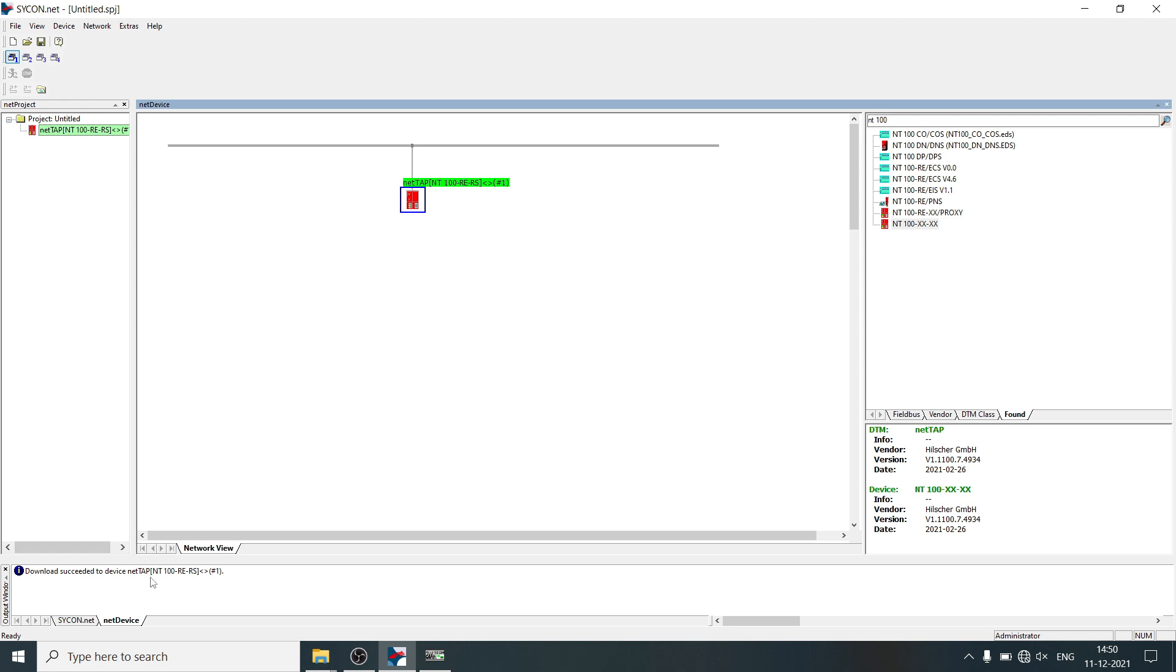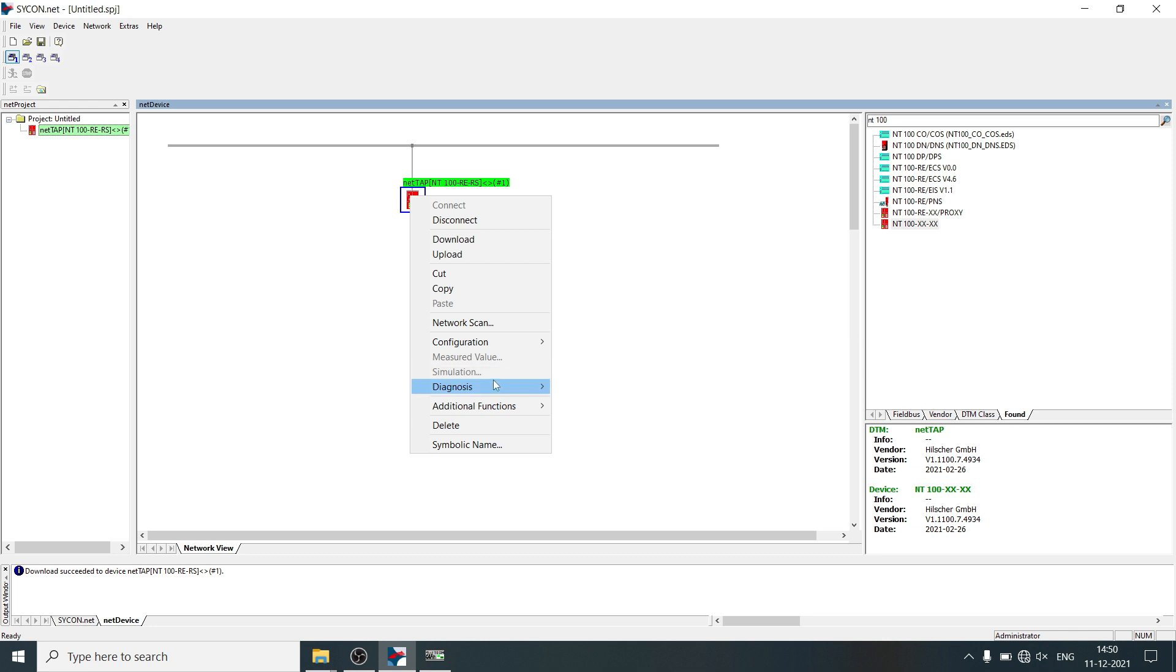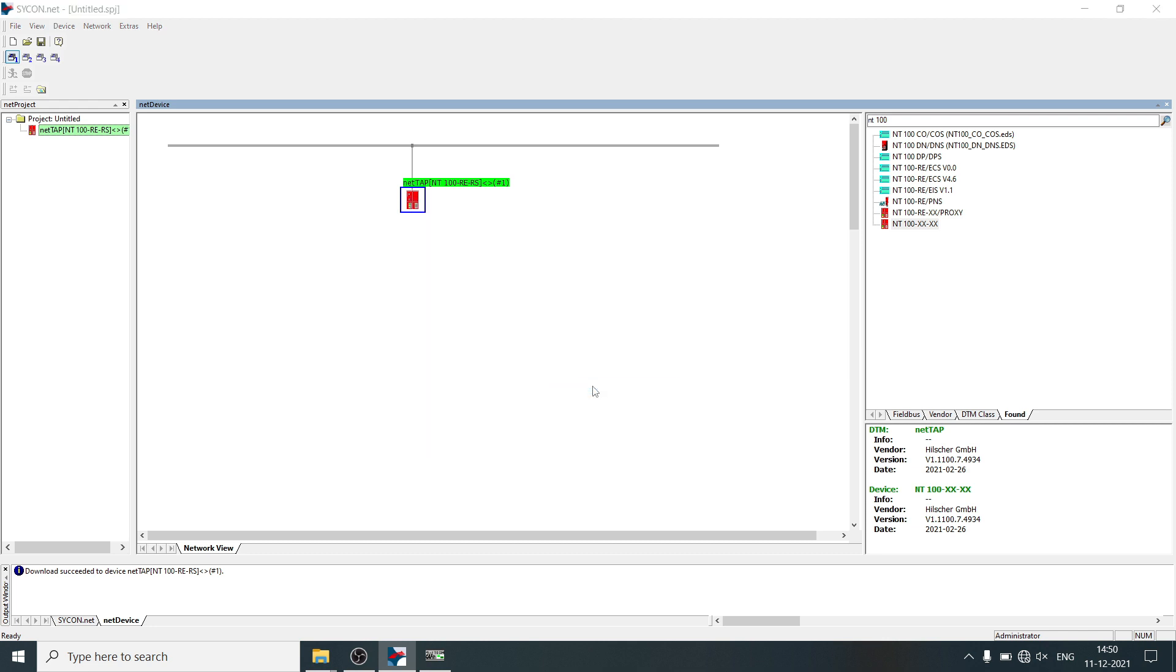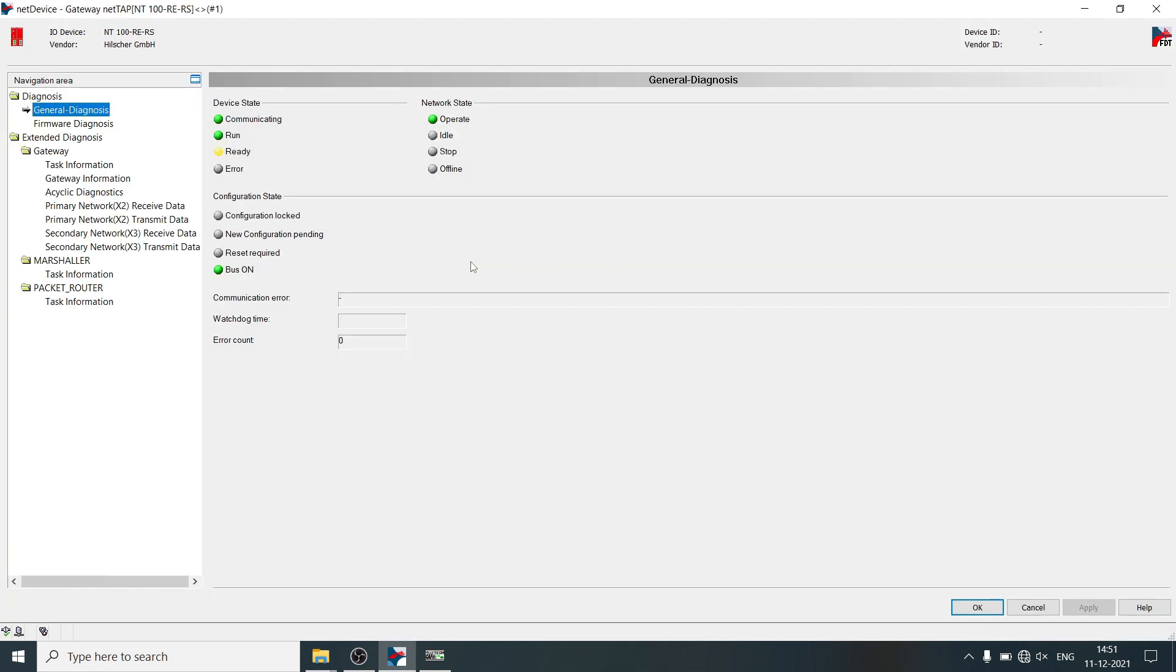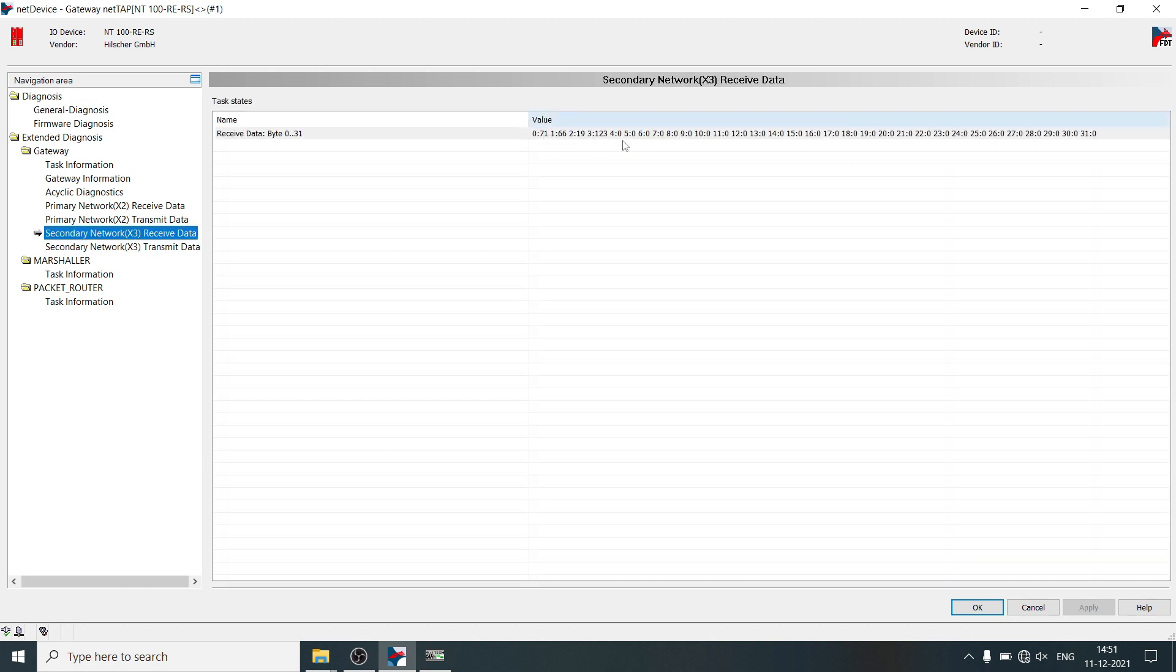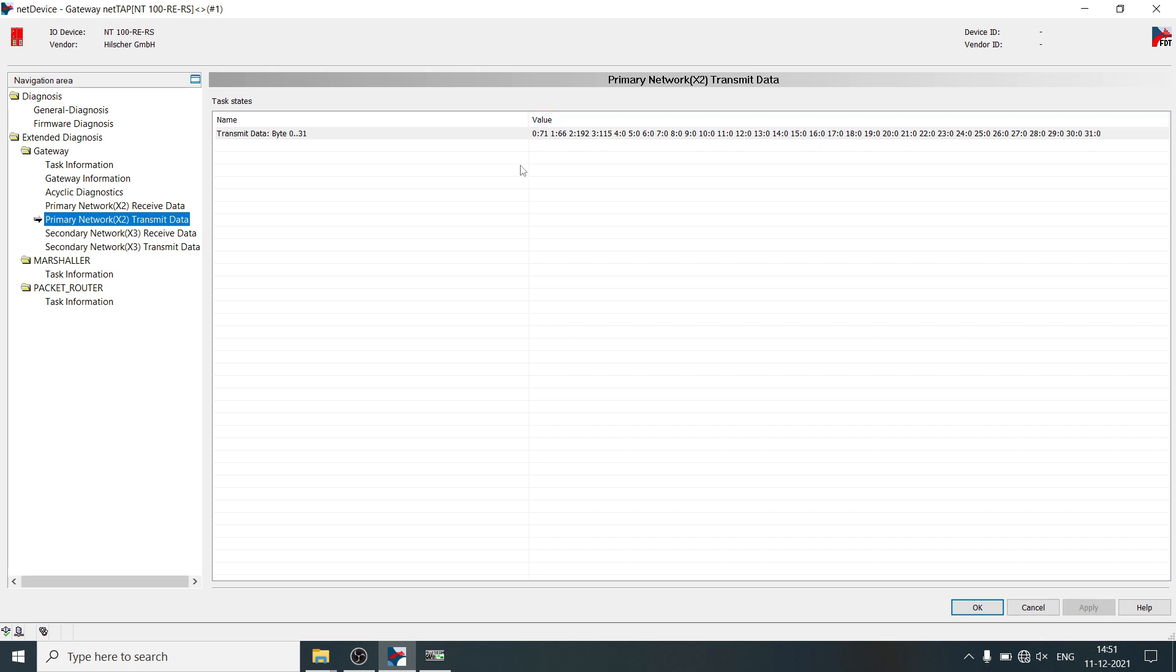We can take a look at diagnosis, right-click on netTAP, select diagnosis, gateway. In this example everything is working properly, proper communication and mapping can be checked from receive and transmit data. This shows data from Modbus RTU energy meter, and this same data transmitting to the Modbus TCP client application, thanks for watching the video.